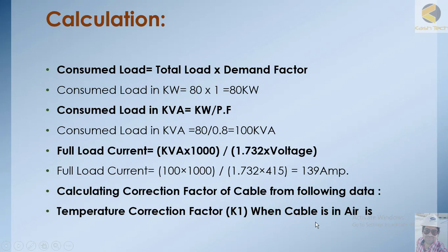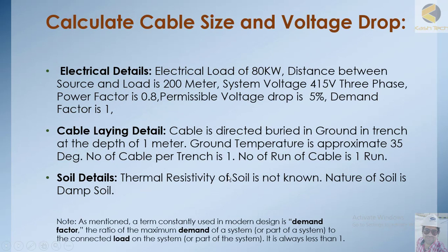Now, to summarize the setup: the load we need to supply is 80 kilowatt, the cable length is 200 meters, the system voltage is 415 volts, the power factor of the load is 0.8, and the permissible voltage drop is 5 percent. The question is which conductor cross-section in square millimeters we should use.